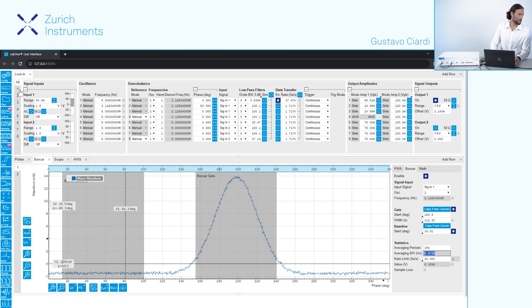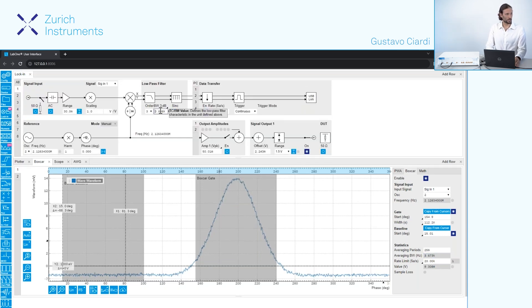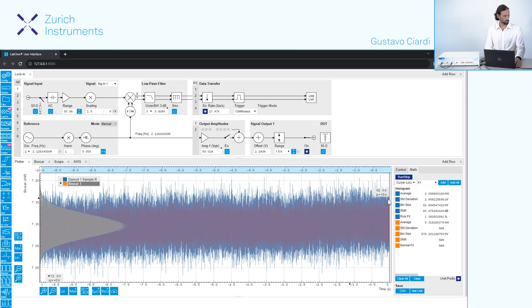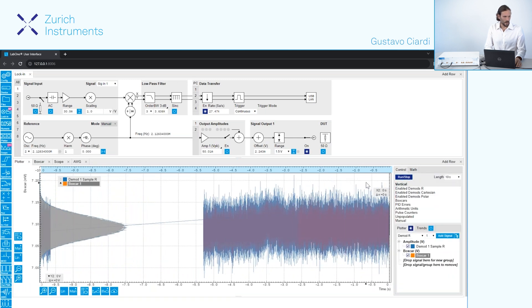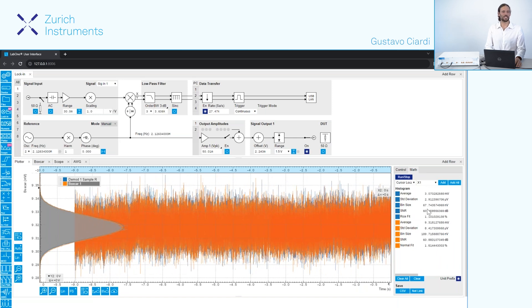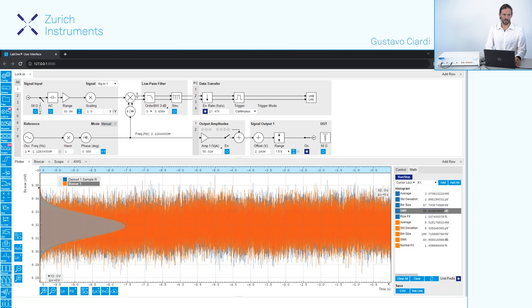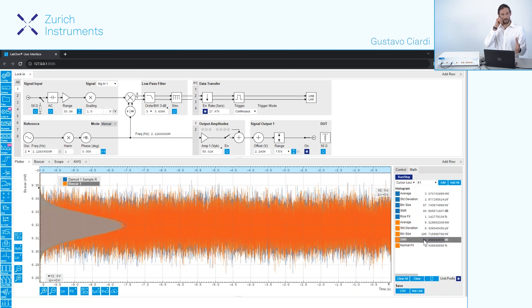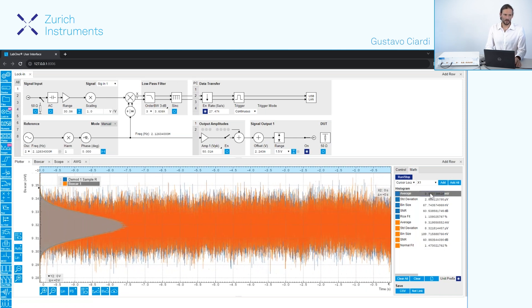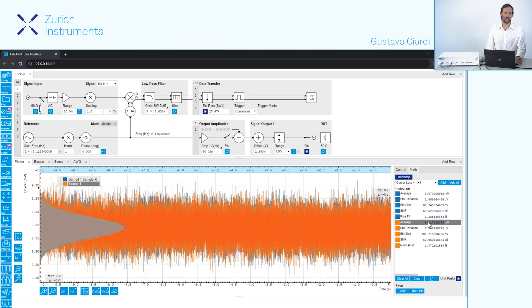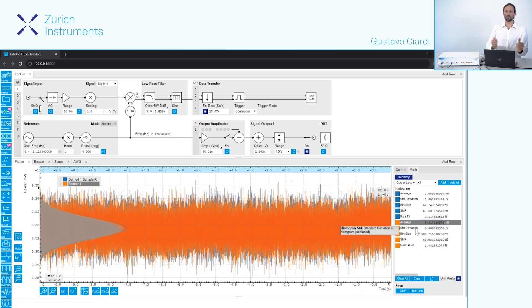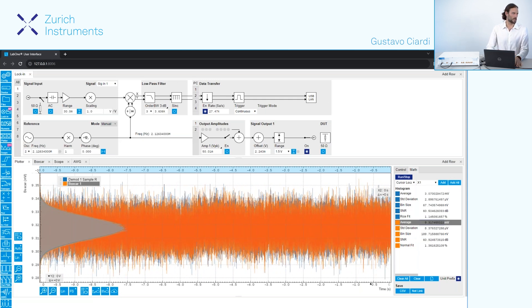In order to compare lock-in amplifier and boxcar averager, we set the lock-in measurement to the same bandwidth so we can compare SNR apples to apples. Running the scope, we can see that in this precise configuration the signal-to-noise ratio of the two measurements is compatible — they lead to roughly the same SNR. What is interesting is that for the lock-in measurement (the blue line) we measure an average of about 3 millivolts, while for the boxcar averager we measure a higher average value because we are integrating and summing contributions from the higher harmonics.